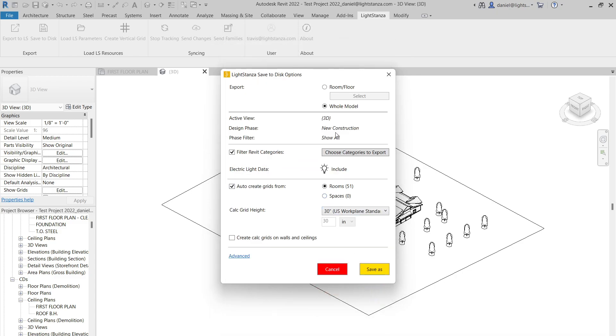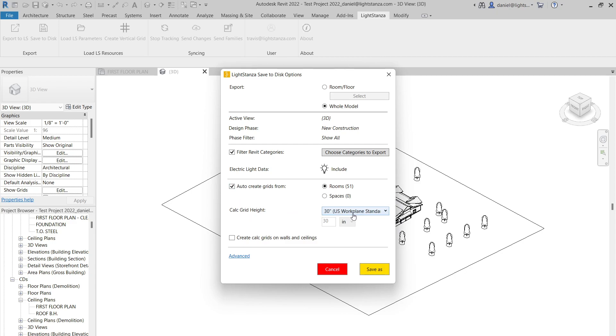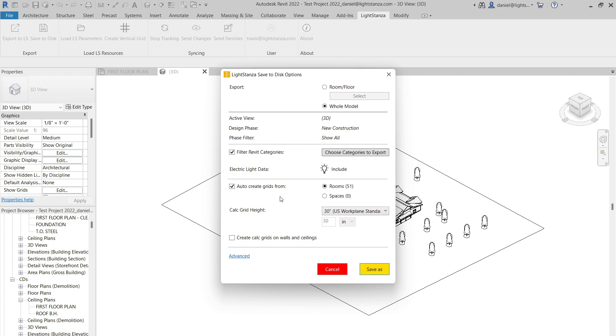So once that's selected, just hit OK. They can exclude or include the light fixtures that are already in the Revit model. Maybe you want them to send you just the building geometry so you can start from scratch. Maybe they already have a basis. Maybe you're doing an alternate package for them and you want to sub out light fixtures. So in that case, you would want them to include that. And then Light Stanza also has the option to auto create grids. It defaults to 30 inches, but you could have them enter any value in here, a custom value. But don't worry, if your client sends the calc grids at the wrong height, they're really easy to change once it gets into Light Stanza.